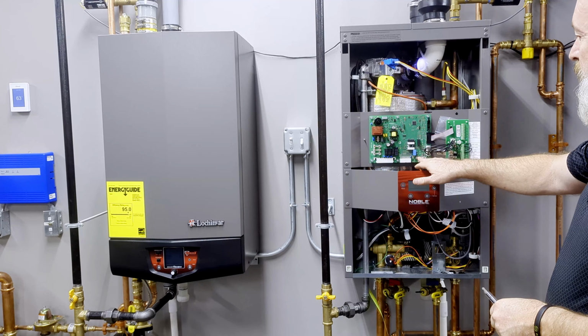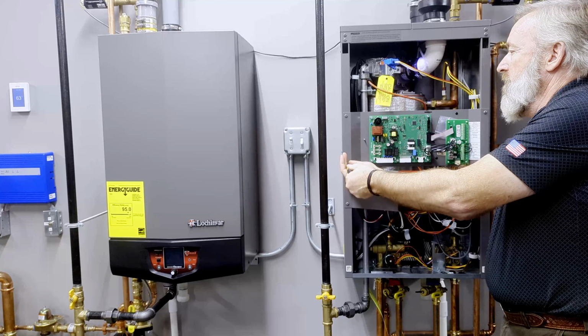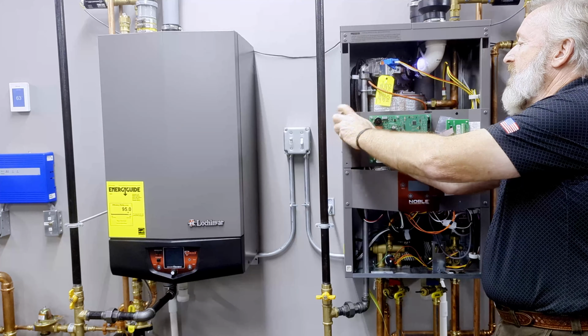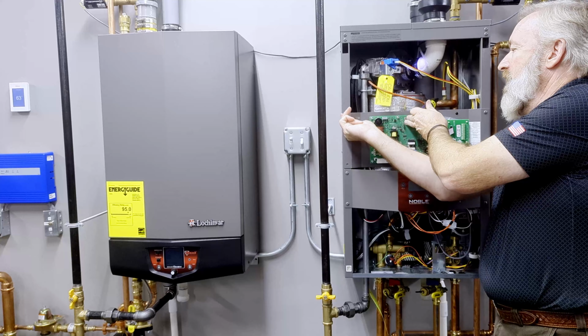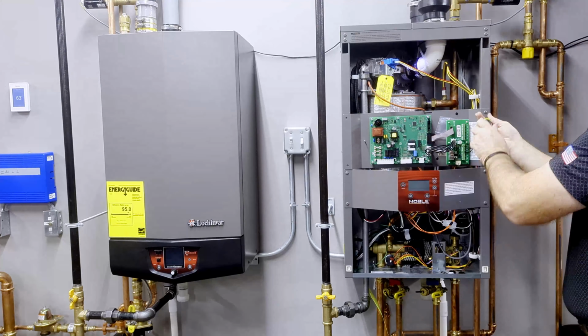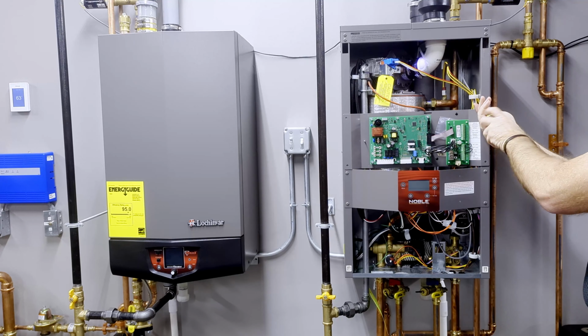There are 4 connectors on the main board, and there are 2 connectors on our low voltage board. In this case, one of the second connectors is the optional low water cutoff. So if you don't have an external low water cutoff, then you won't have that connection there. We're going to remove the 4 screws that hold the plate on. When we take those off, these 2 boards are going to come off. Just be sure to have a grip on it so they don't drop down on you.